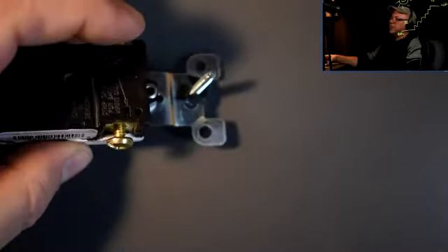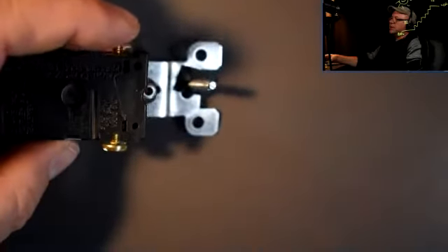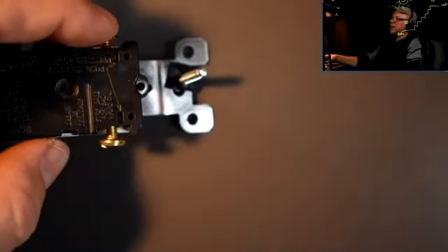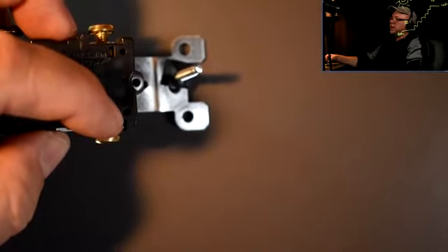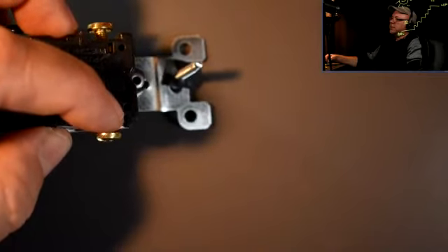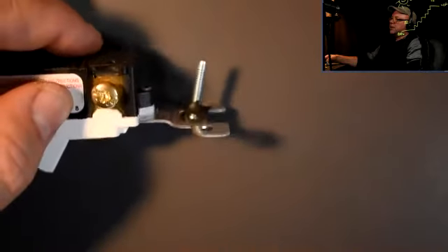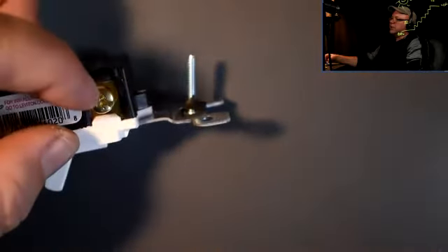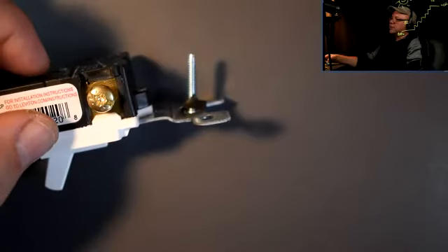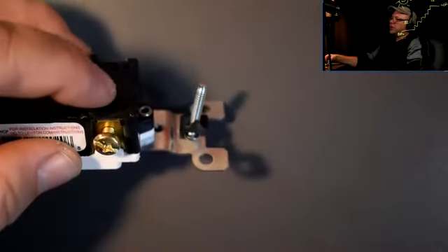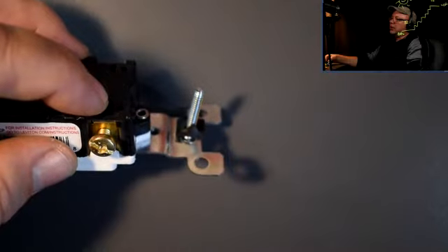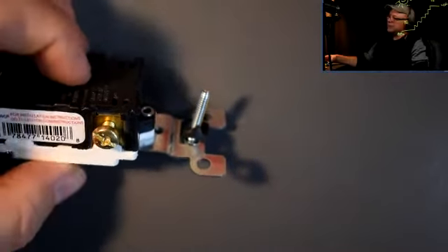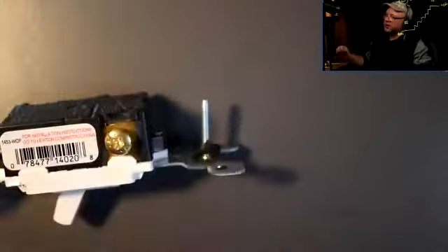It is approved by the inspector, if the inspector is going to inspect your job on the job site, yes, they're going to approve when they see that. But my personal opinion, and many others', is using the screw terminals. Okay? Simply because you don't see that connection. You just don't know how good or how not good this termination is, performed with the backstabbing.